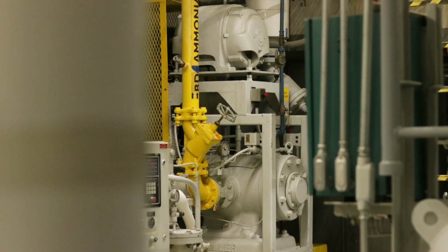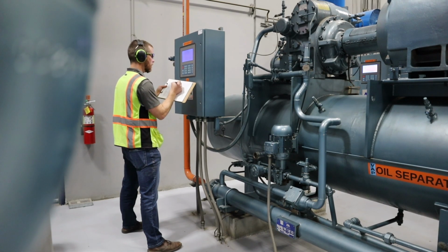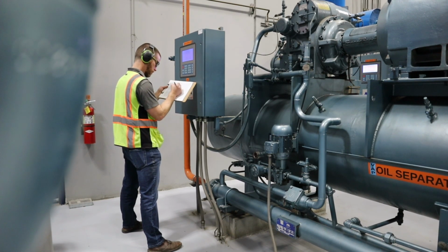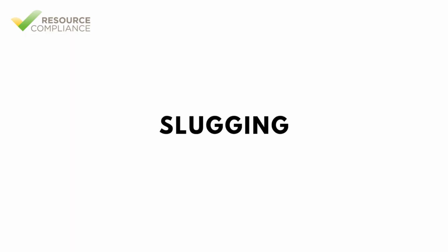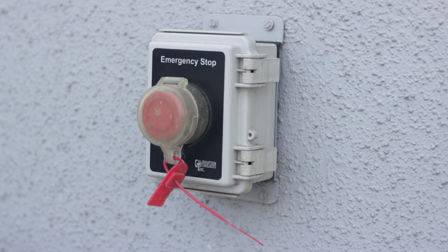Once the suction pressure stabilizes, the valve can be fully opened. When starting a compressor, the operator must make sure that no liquid is allowed to enter the compression chamber. If loud noises are heard at startup, it may be due to liquid slugging. Immediately shut off any compressor suspected of liquid slugging.